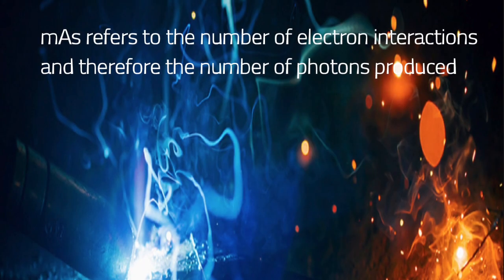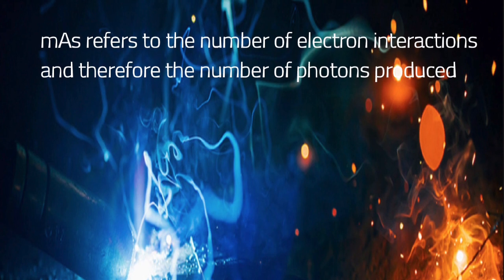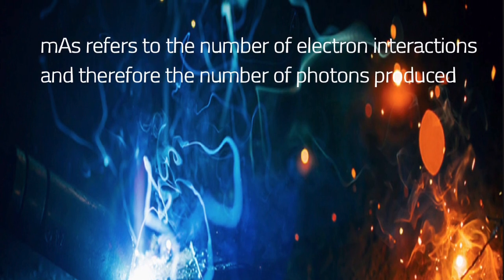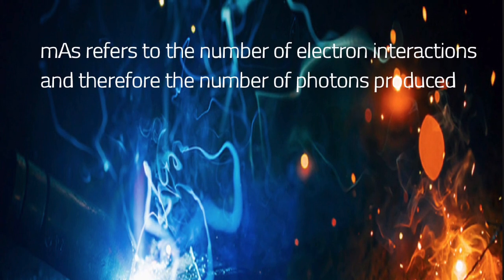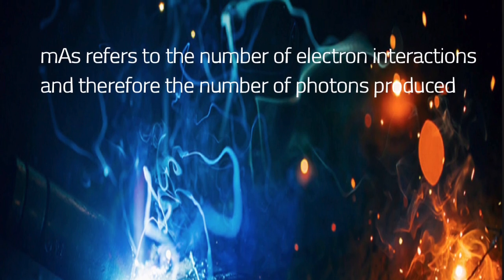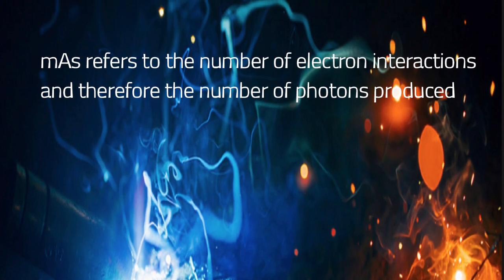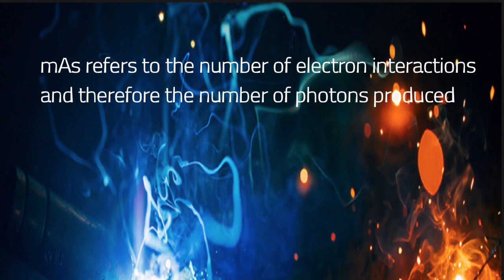Milliamperage refers to the current that is supplied to the cathode and when calculated with time produces the mAs, which has a linear relationship to the X-ray intensity produced. Each milliamperage station should be evaluated using a penetrometer.